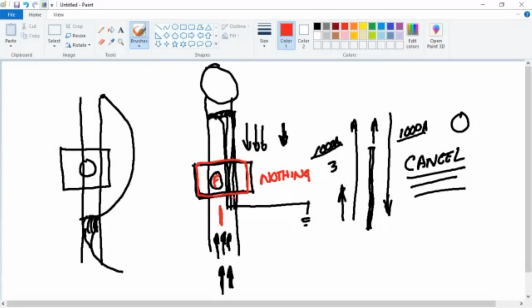Now, some companies want to have that neutral covering all of the conductor that they have. This is the elbow that goes on. So they have better protection around the conductor all the way to the top. Leaving this exposed in this area does not give good neutral protection around the conductor. So it just depends on your organization and where you're going to be installing it and what they do.